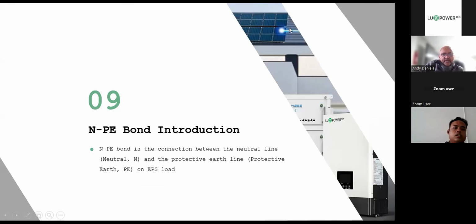All right, so that's coming to point number 9, which is the neutral protective earth bond introduction. There are some of you who are certifying engineers, and you need to know about the neutral earth bond. The neutral earth bond, as you know, with the SANS code, any power generator that is connected, that puts out AC power that's connected to your house, must have a neutral earth bond, because the supply that we get from the utility or from the grid in a typical setup is bonded.